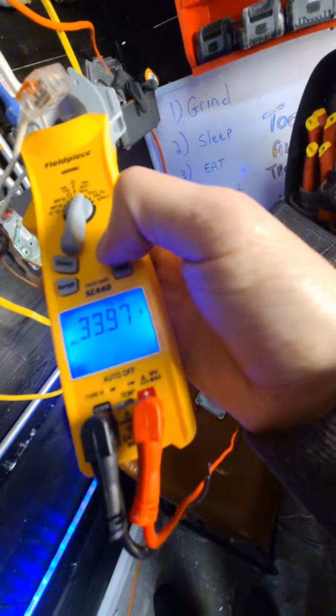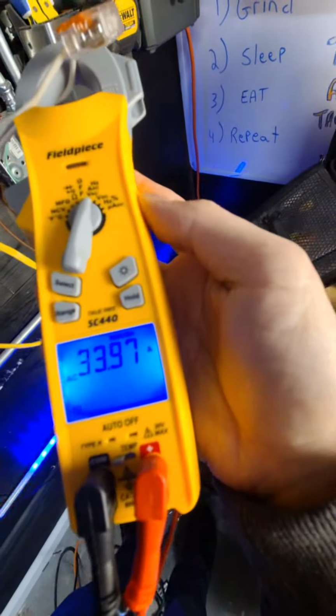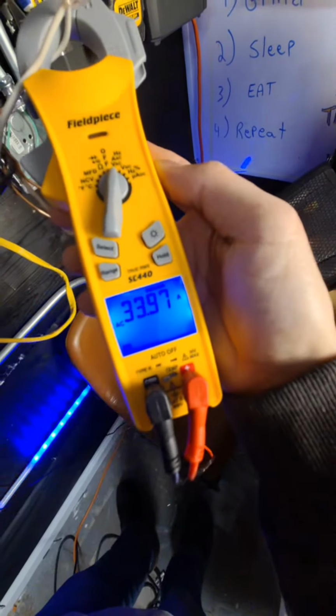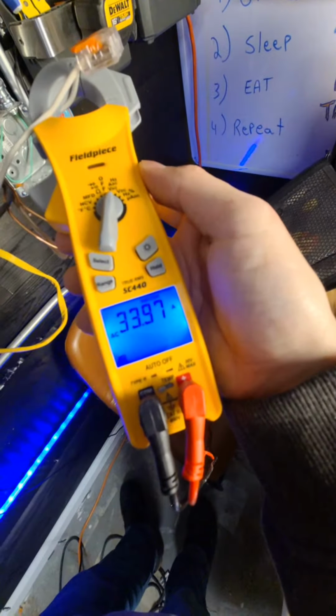I believe it's 6 times - is it 6 times the regular current for inrush, or is it 3? We're gonna find out, we're gonna turn on this saw. Saw is off. We've already captured the inrush on it, so let's see what it is. Inrush current is 33.97 amps. And that's how you do inrush.